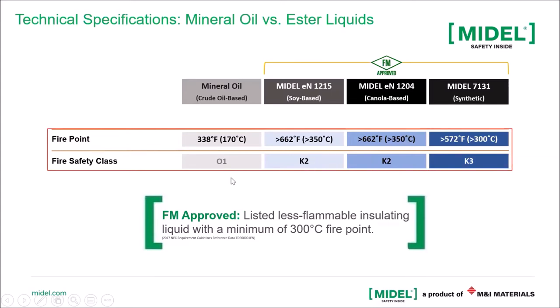And this represents really the net calorific value of the fuel source. The higher the number, 3 being the highest, means it has less calorific value if it was to be consumed in a fire. So the MIDEL 7131 gives you the highest fire safety class with a K3. Mineral oil gives you the lowest. And the natural esters are K2, which is still very good.